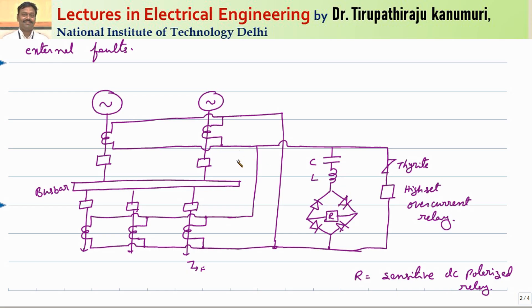For the case of internal faults, because of the L and C effect, sometimes high voltages may be induced. To avoid spoiling the circuit, a thyrite resistor is used, which acts as a short circuit for high frequencies and as an open circuit for low frequency components. Whenever the high frequency component comes, it is bypassed through the high-set overcurrent relay. This high-set overcurrent relay operates only for higher values of current. For external faults, only the difference of the two CT characteristic currents passes — not the complete fault current — so this high-set overcurrent relay should not operate.